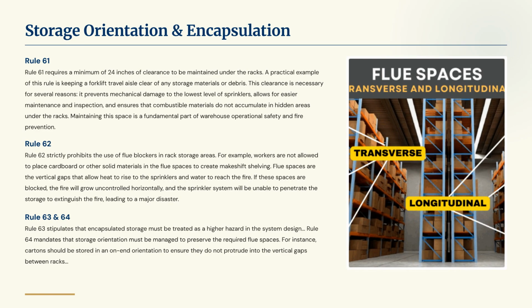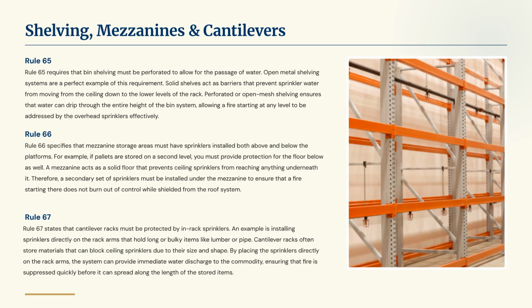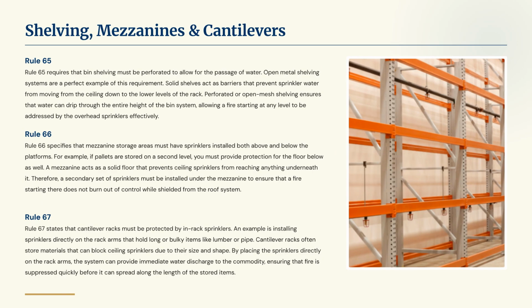Rules 63 and 64 relate to treating encapsulated storage as a higher hazard and managing storage orientation. Rule 65 requires bin shelving to be perforated for water passage. Rule 66 specifies that mezzanine storage areas must have sprinklers both above and below. Rule 67 mandates in-rack sprinklers for cantilever racks.